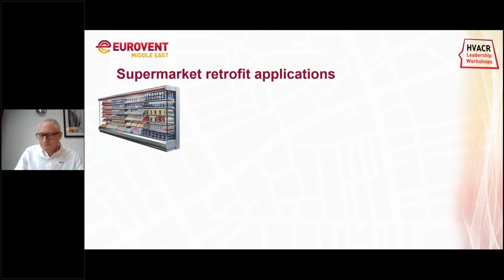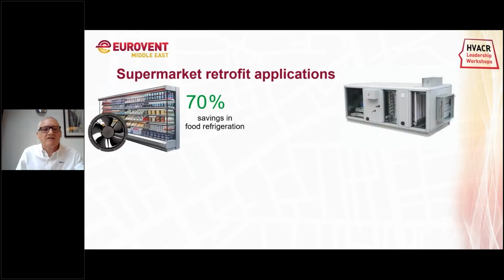Okay, so first of all, display cases. I think Andreas in the first slides talked about EPTA and their case designs. Yes, we supply them with energy saving motors, and just by changing the motor out, it's a 70% energy saving. It's quite easy, and it doesn't have any detrimental effects on the refrigeration system. In actual fact, it enhances the refrigeration system. It's a very, very easy retrofit, and the speeds and the airflow can be maintained exactly the same as the original fans. I've got a case study later on that I'm going to explain, so I'll go into a little bit more detail about that.